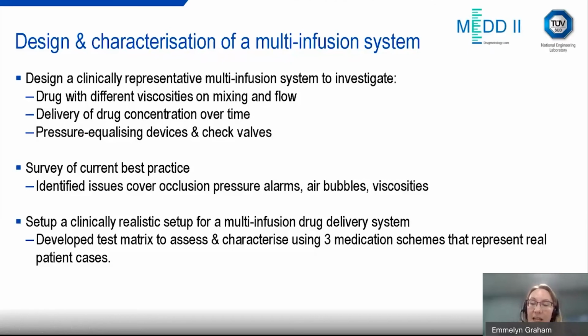There was a model developed in the previous project, and all this information is again available on the website. So we're looking to extend that multi-infusion model to include other issues, for example check valves, different concentrations and mixing, to then investigate the effect. We are going to be setting up a clinically representative setup for a multi-infusion system, and this has come from our interviews with the hospital staff. So we've developed a test matrix and we have all the equipment, the equipment that they would actually use in a hospital, and the actual syringe pumps that we are going to be trying out and testing. We're going to characterize 3 different medication schemes that actually represent real patient cases.